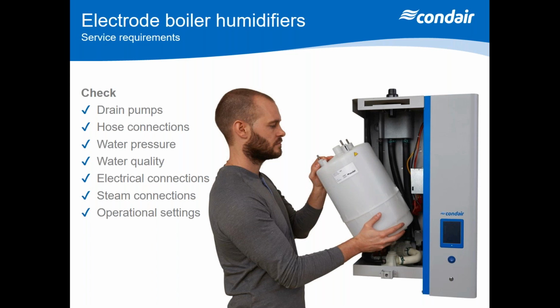And obviously the number of changes or number of service intervals will be determined by how hard your water is. Now, if you don't know what your water hardness is, it's always worth having a look at the water authority that you're being fed by your postal code, and they will give you some readouts of what your hardness levels are. And conductivity is what we tend to work on. So if it's over 500 microsiemens of conductivity, that is what I would class as hard water, or very hard water if it goes even higher. Okay, that's the electrode boiler.